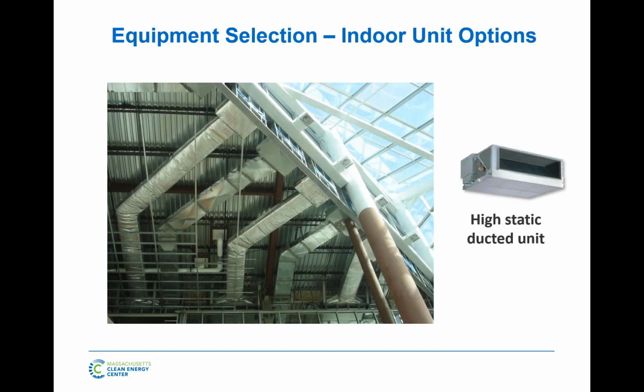All the way up to your conventional larger, you can get a high static ducted unit, an 8-ton ducted unit that's serving a very large space with a lot of conventional ductwork. Not going to be your most efficient option. Again, this is back more towards the way conventional systems are designed without much zoning, but it's a possibility and fits certain scenarios. You might use something like this to do the entire atrium here in the building.